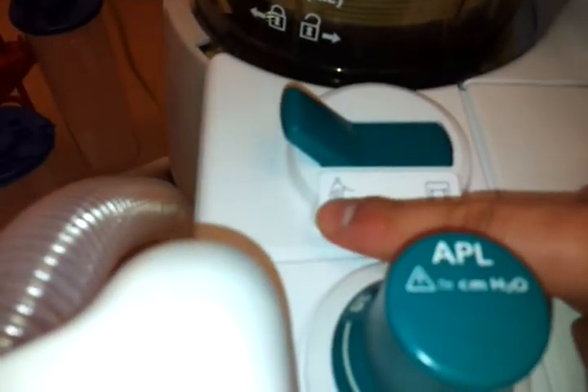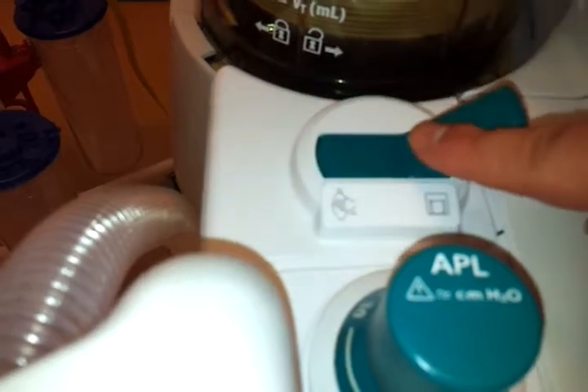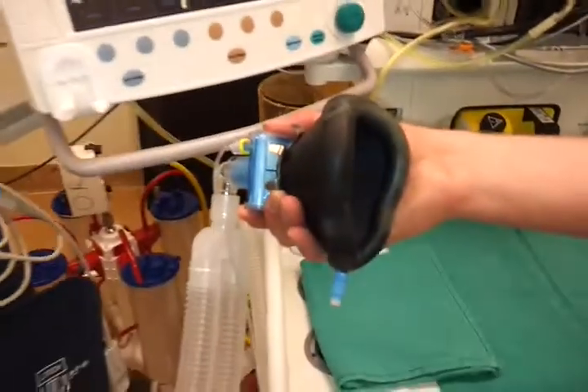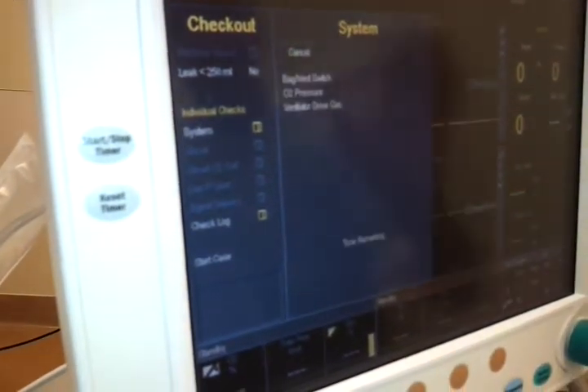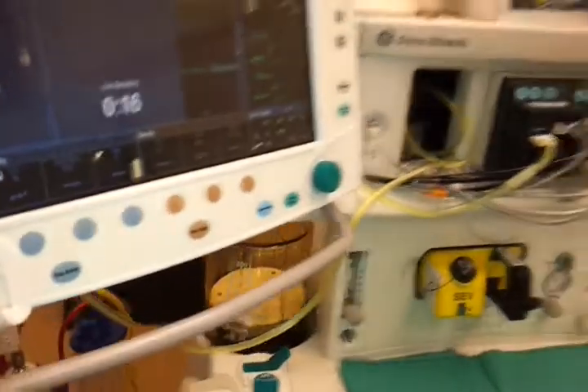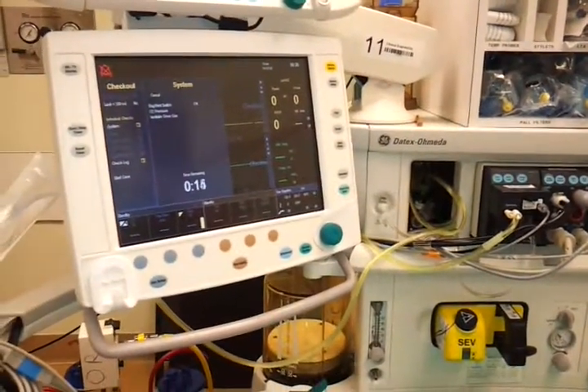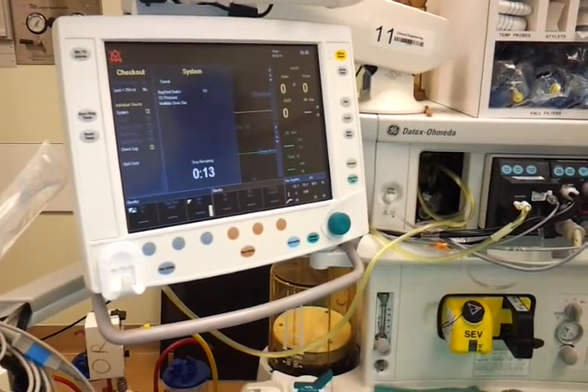You can see a little picture of the ventilator and the bag. It's set on bag right now, so you're going to switch it over. You want the patient Y opened, so you want this open to atmosphere, and then start. So basically you just have to hit start. This one only takes about 20 seconds. So we're just going to let it go.